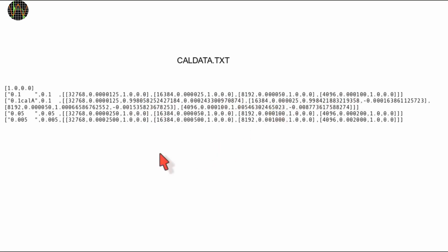For ease of comparing calibrated and uncalibrated current data, I actually created a second line for my built-in 0.1 ohm shunt and called it 0.1 cal-A. So all I need to do is to switch in setup to that shunt, and the unit will use the calibrated numbers I added into the slope and intercept fields. This calibration occurs, of course, in my software.